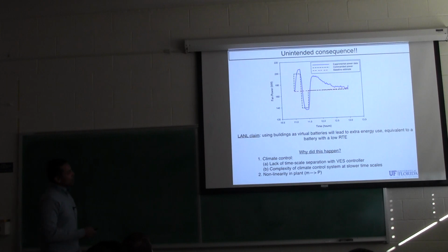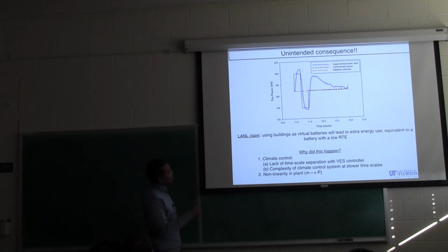This is what they claim, and this is an experimental result from that paper. They said, look, this is what happens if we try to change this power consumption quickly, by changing the set point. Here, this black line is the commanded power consumption, and this red line is the baseline. They want to increase from 160 to 200 kilowatts.